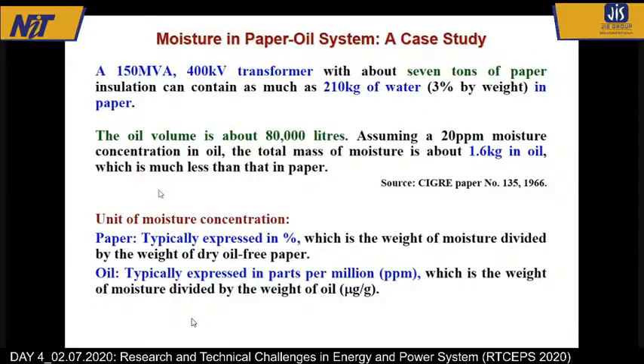Generally, paper moisture is always expressed in percentage by weight. Oil is typically expressed in parts per million. Now, when you say parts per million, I always ask a very simple question. How do you measure parts per million? Do you cut that sample into a million parts? The answer is no. It is very simple. Again, this is a fact to always keep in mind. You take one measurement and measure how much moisture is there. If there is 1 microgram of moisture in 1 gram of oil, it is 1 part per million.